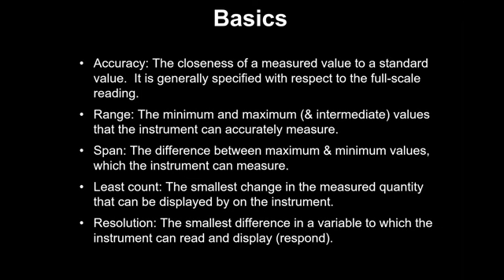If our sensor can pick up 0.01, then correspondingly the resolution of the sensor is 0.01. Of course, when we are buying a handheld or portable instrument, they will match the least count and resolution so that ultimately we get the correct value. But many times we do data logging also, where data loggers are separately procured and sensors are separately procured. So there this aspect comes into play: when you're buying a sensor, we have to see the resolution part, to see what is the least difference it can measure, the variation in process, how accurately it measures, to what decimal it can measure. So these are the things we need to understand and take care of.